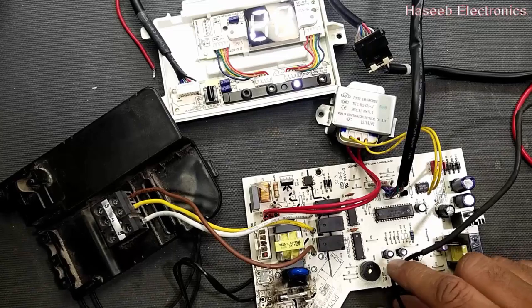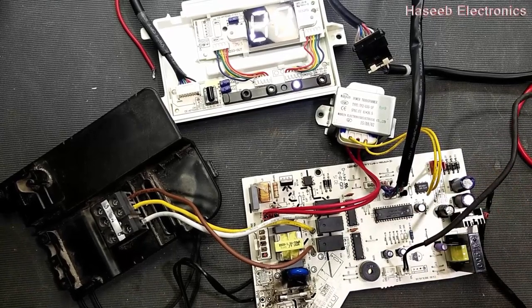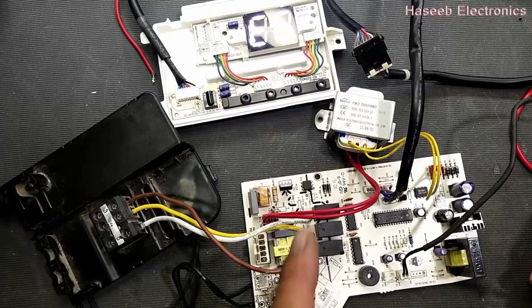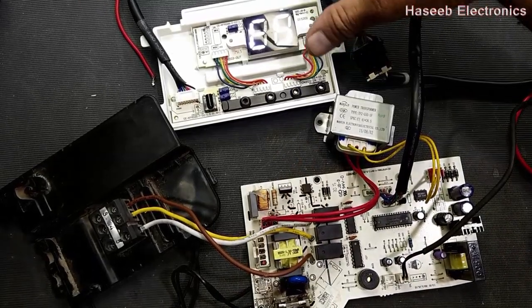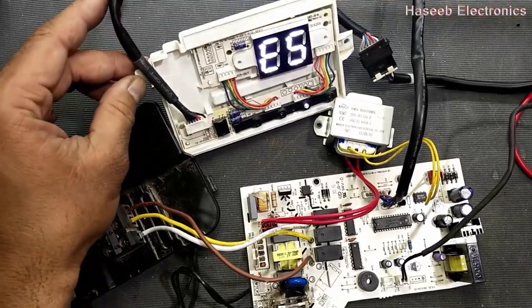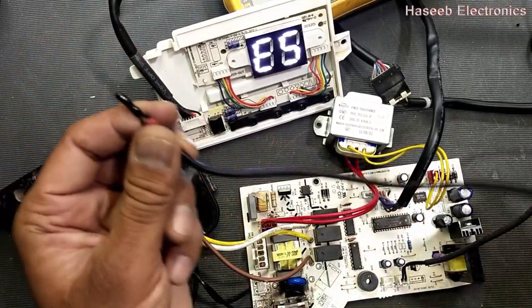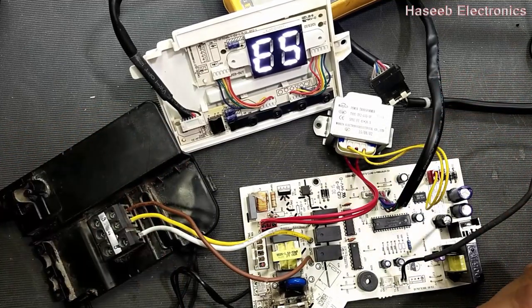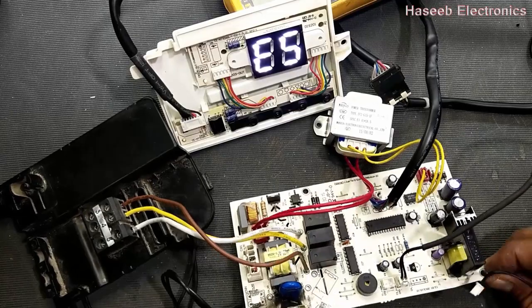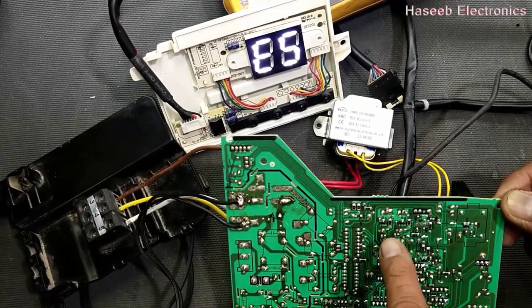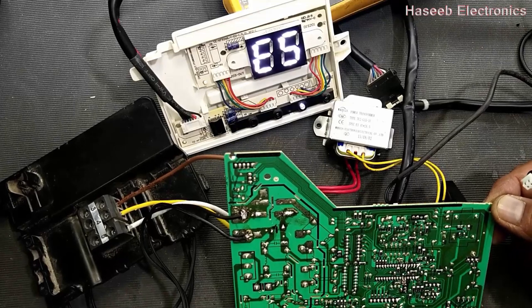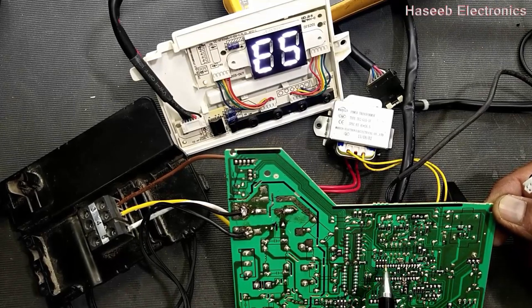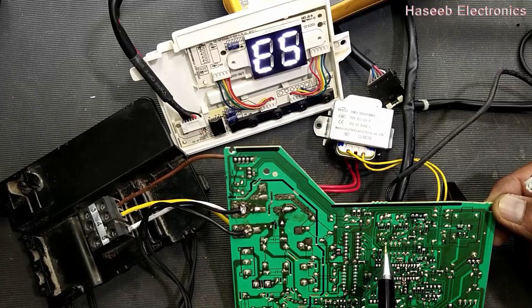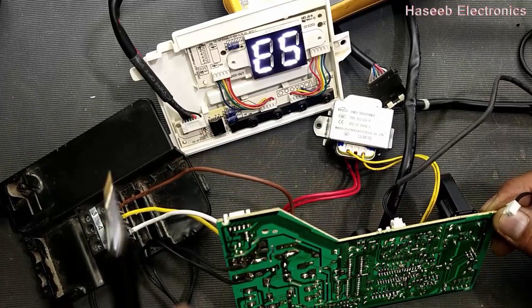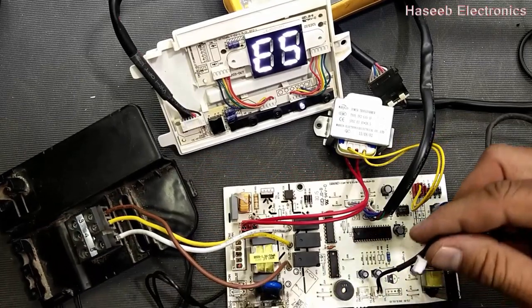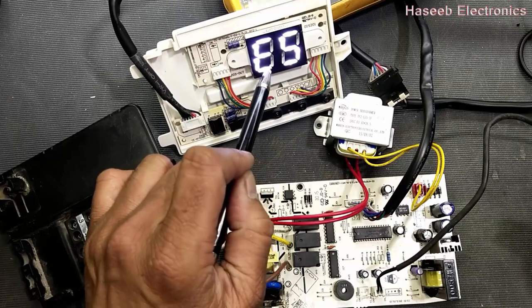Now, if we find this temperature sensor bad, it will give an E5 error. That means the room temperature sensor or its cable or its connector is faulty, or maybe here we have a transistor at this point. This transistor, this line, the first left line, if it is not communicating, it will generate an E5 error. The light will blink and it will display E5.